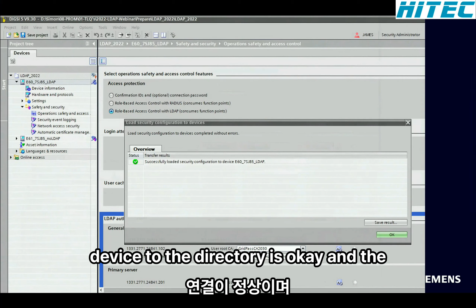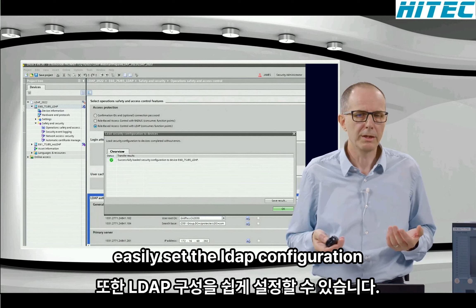If the Ethernet connection from the device to the Active Directory is okay and the user is included in the Active Directory user group with a role ID according to IEC 62351, the access control settings are successfully loaded to the device. So with DIGSI 5, the well-known SIPROTEC 5 engineering tool, you can also easily set the LDAP configuration.